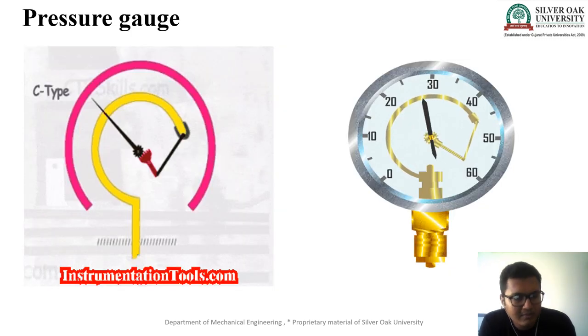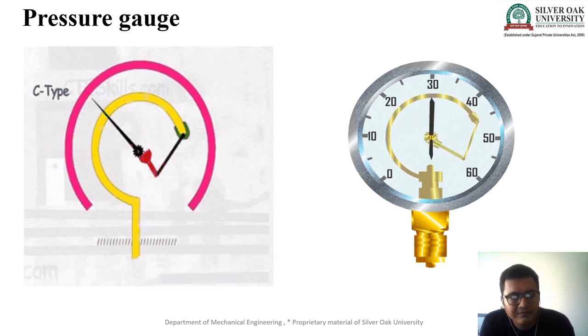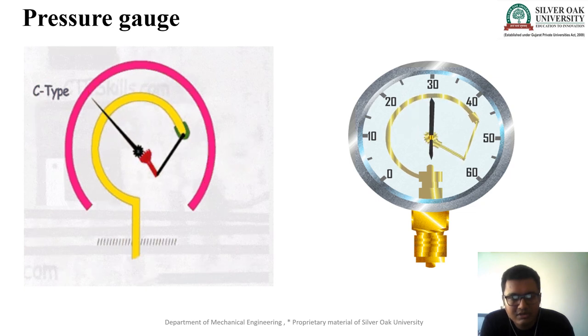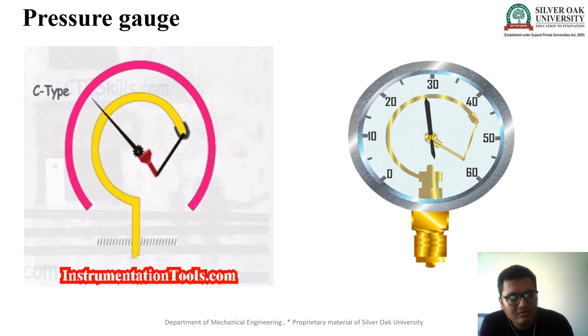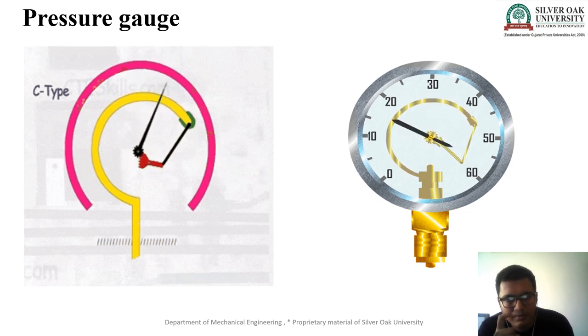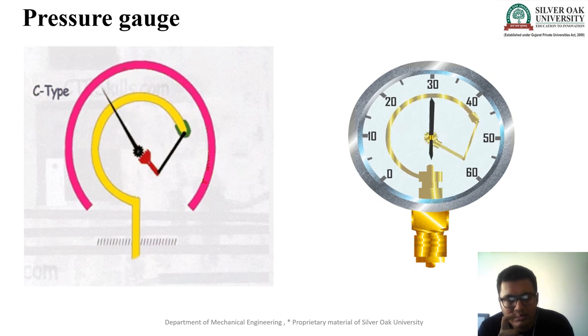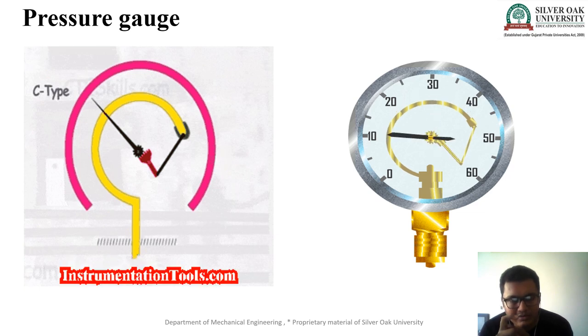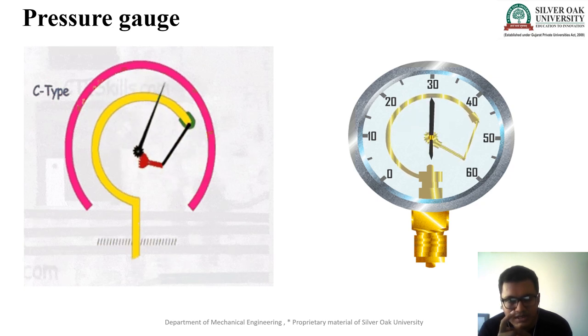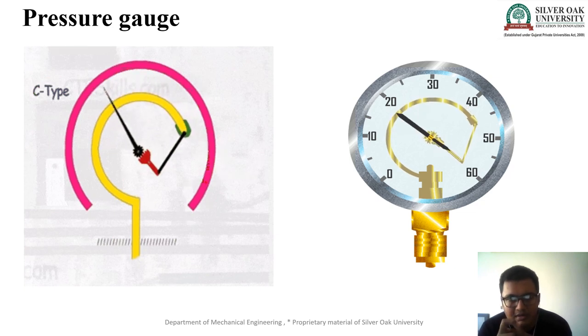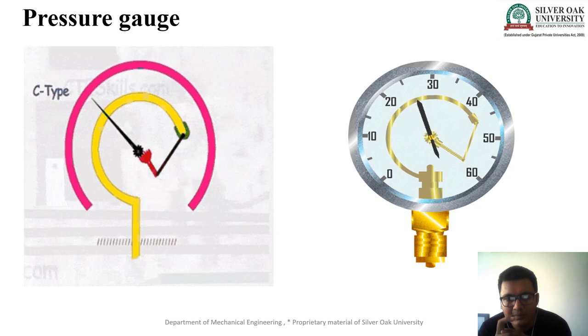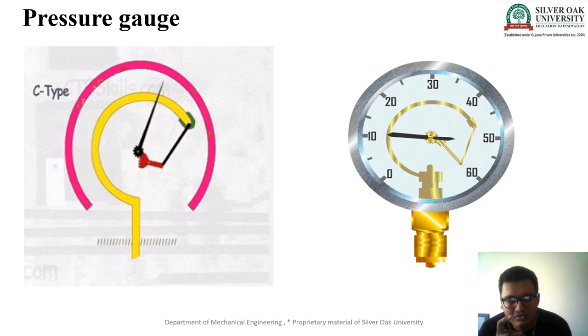Now the second mounting: the pressure gauge. By its name, it indicates the pressure of steam inside the boiler. There are two figures shown. In the first figure, a C-shaped material called the Bourdon tube is used. When pressure enters the Bourdon tube, it tends to straighten. As it straightens, a pointer connected via a rack-and-pinion mechanism moves on the dial gauge. If pressure is removed, the Bourdon tube returns to its original shape and the pointer shows zero.